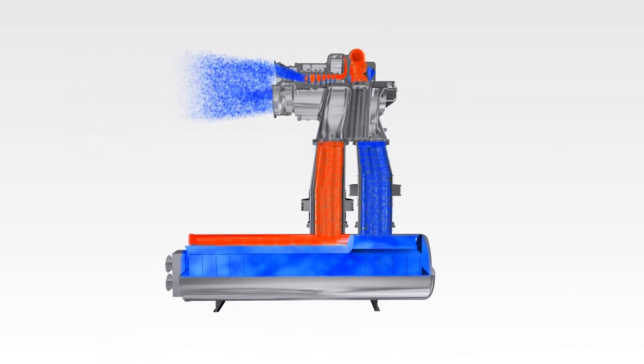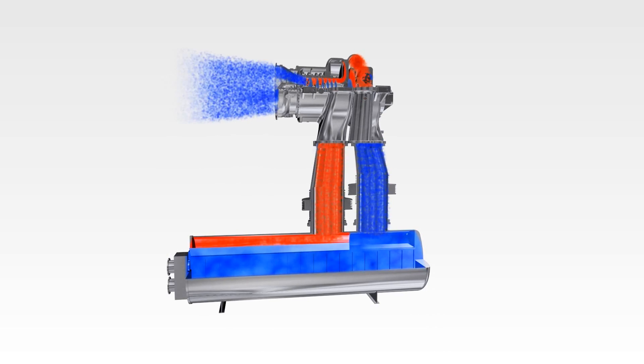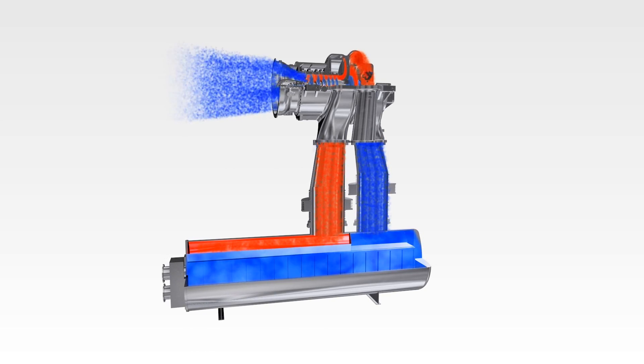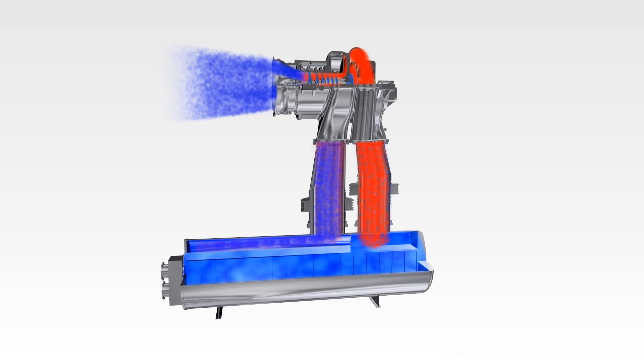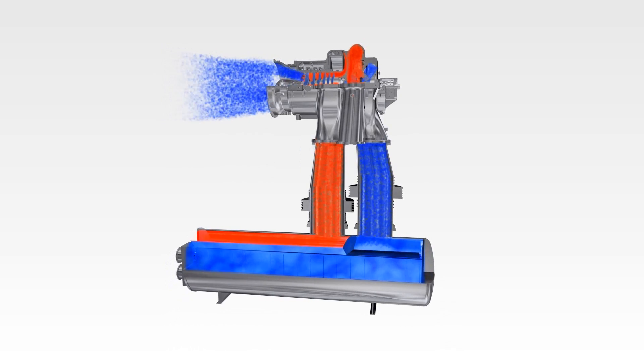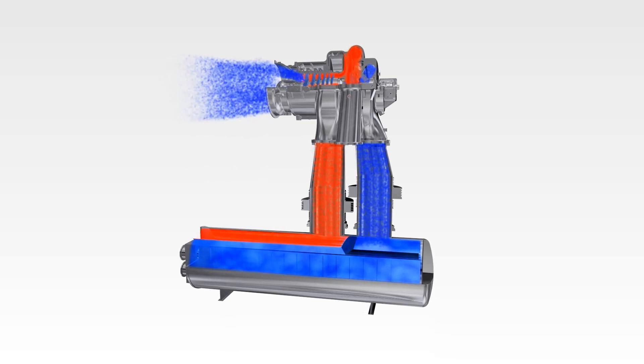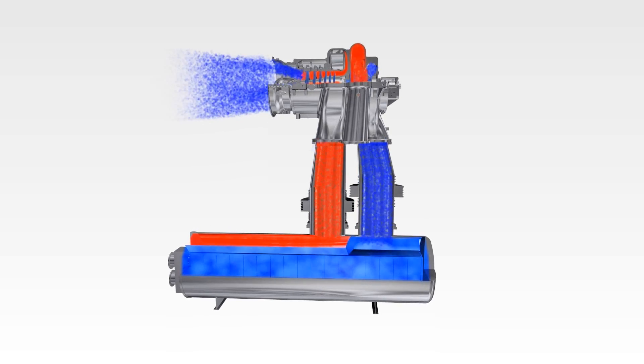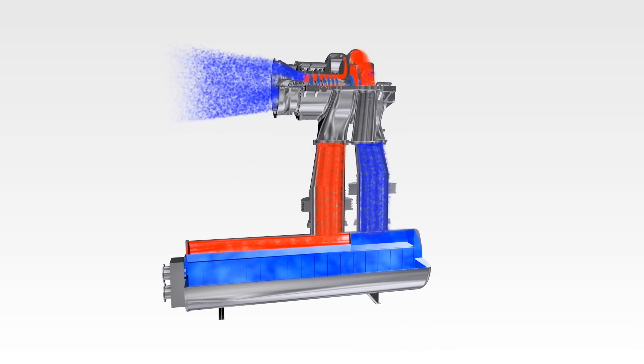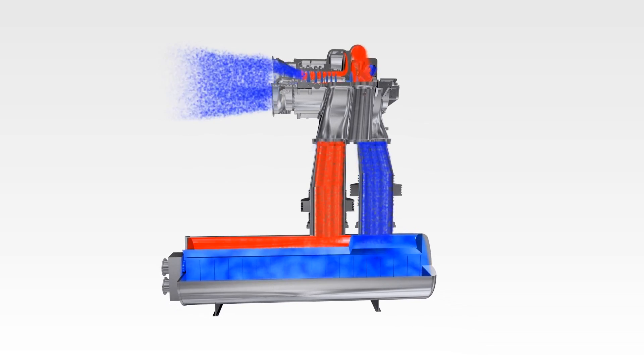The Max 1 wide chord blading has a strongly improved robustness against all kinds of mechanical blade loadings. Compressor surge is usually the most dangerous flow instability for conventional axial flow compressors. This periodic backflow occurs when the back pressure is too high for the compressor. During surge, the energy of the huge pressurized air volume inside the intercooler relieves by the air flowing back through the axial blading.